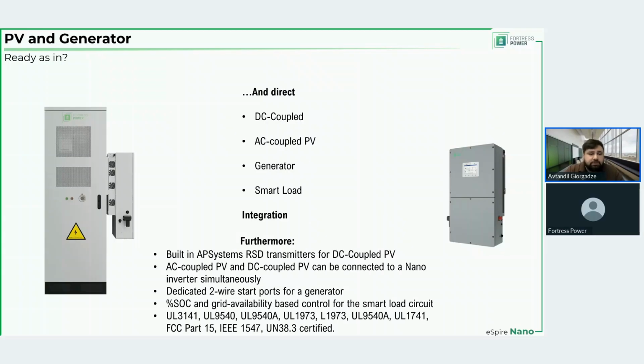As I mentioned before, this system is solar and generator ready. This is ready for both AC coupled and DC coupled PV. For DC coupled PV, it has a built-in APS transmitter, which works with the APS receivers, as we will see momentarily. And AC coupled PV directly connects to its smart port. So you can use that port for the generator, for a smart load, or for AC coupled PV.